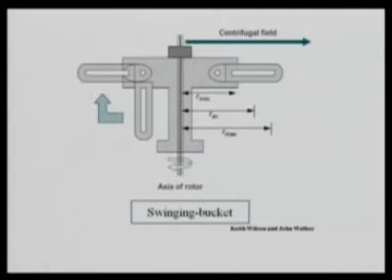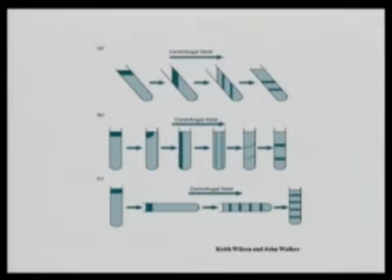So like this, in this rotor, that is the swinging bucket rotor, the centrifuge tubes are being rotated from vertical to horizontal positions. But remember one thing, they are not rotating continuously. Once you switch on the instrument, they are going to take this horizontal position and rotate for a certain time. Once you switch off, again they come back to the same position. Hence we call it the swinging bucket model of rotation.